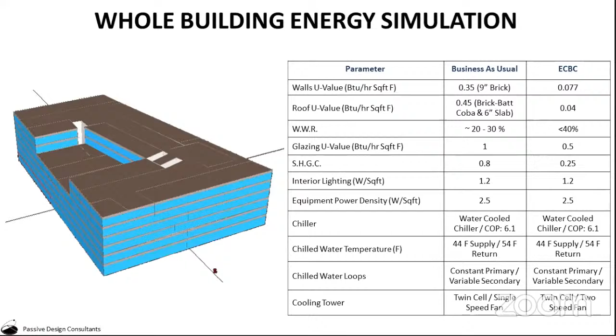We also used a whole building energy simulation approach, which is one of the compliance methods in the Energy Conservation Building Code in Punjab and in India. And we used the energy model to predict and optimize the building design. I told you what kind of design we received from the client. The project basically had 100% glass throughout the building on all 4 directions. So we started with the very basics of optimizing the window to wall ratio, which is the amount of windows we have. So instead of having structural glazing on all 4 facades of the building, we proposed to the client and the architect that we must reduce our window to wall ratio. And as per the ECBC recommended value, the WWR, or window to wall ratio, should be below 40%. For the project, we analyzed that it should actually be around 32%.